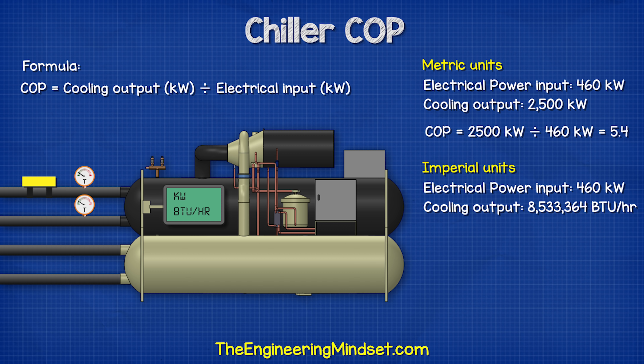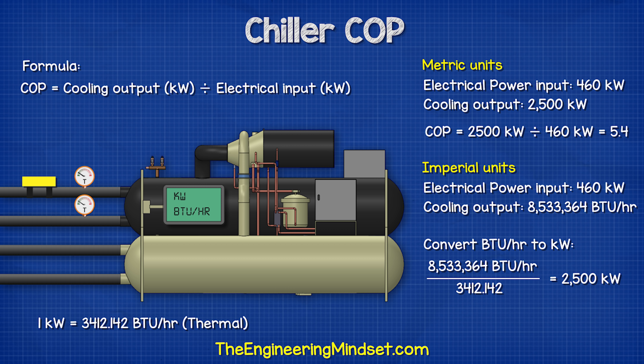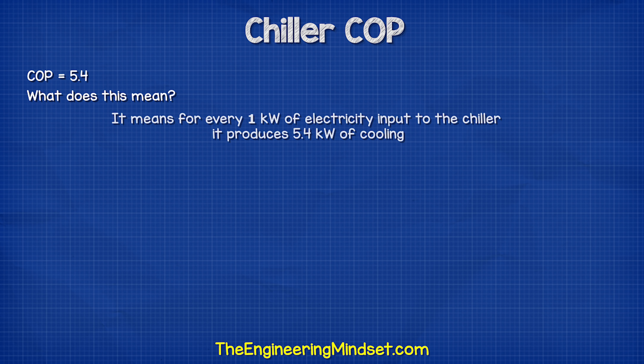When using the imperial units, the chiller is demanding again 460 kilowatts of electricity and providing 8.5 million BTUs per hour. We need to convert that into kilowatts, so we divide by the conversion factor of 3,412 to get 2,500 kilowatts. Then we drop those numbers in to get a COP of 5.4. This means that for every 1 kilowatt of electricity we input into the chiller, it produces 5.4 kilowatts of cooling.